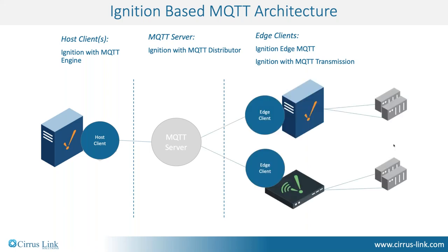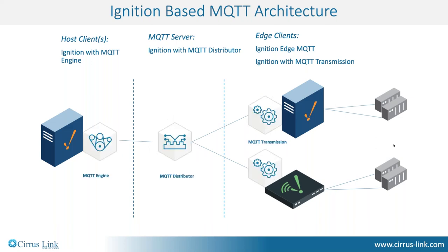Looking at the architecture, we start with the MQTT server where different host clients or edge clients connect. On the left side you have a host client — the hub or central connection point of your MQTT application. On the right you have the different edge clients. The Transmission module can be plugged into Ignition sitting in front of a factory floor with hundreds of thousands of tags. Ignition Edge MQTT is used for remote applications — oil and gas, wastewater, anything with remote capabilities. These all connect into the MQTT Distributor module, to which your central hub application on Ignition connects with MQTT Engine.